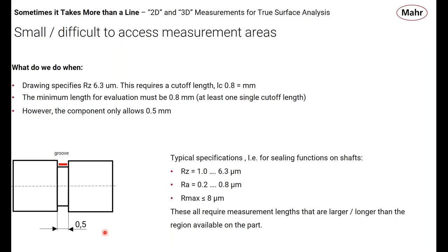So a single half a millimeter long trace with a stylus, I would argue, is probably not the optimal technique for this. The data density is just not high enough for me to be confident that you're really representing that surface. There's absolutely arguments against what I'm saying, but that's what I'm proposing to you right here.